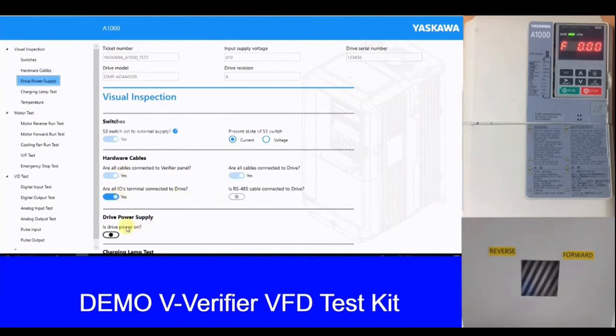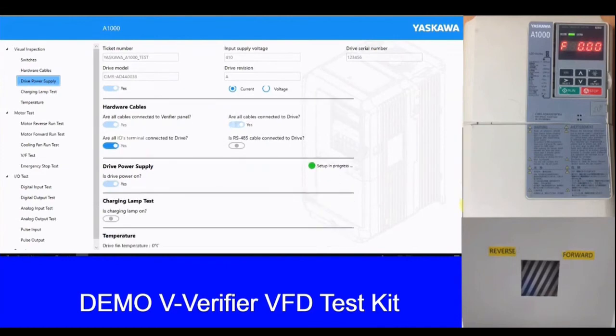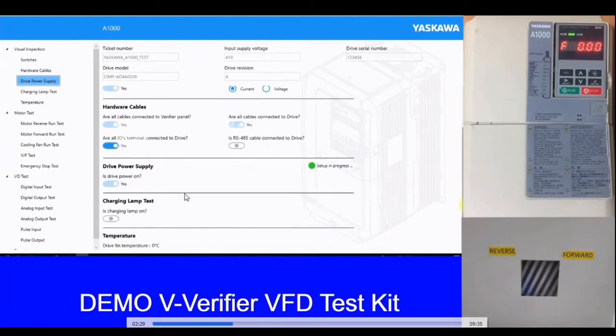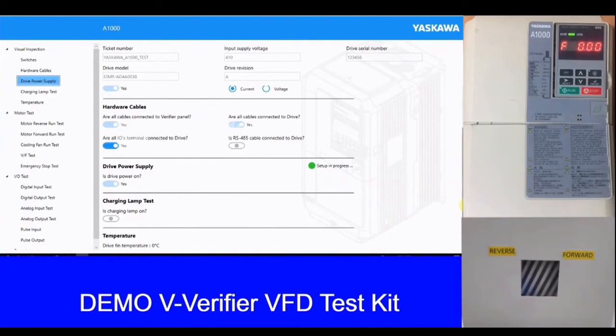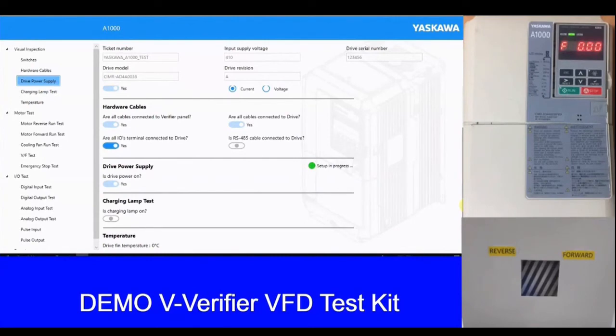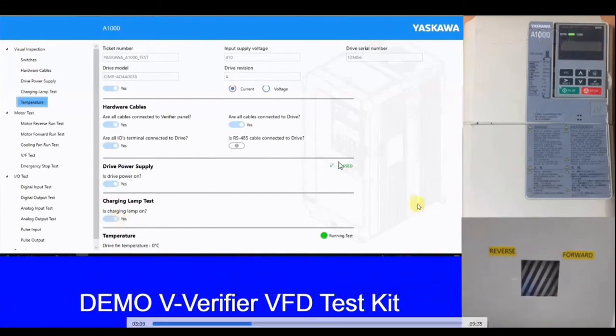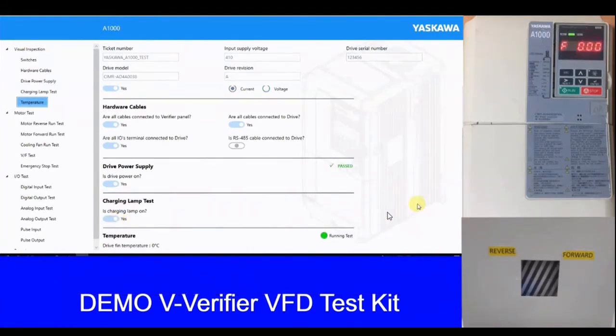Once everything is connected, we press the drive power on button. The initial setup in the VFD begins — required parameter verification and other checks will start. This will take some time. Once the initial setup is complete, we proceed with the charging lamp test, which is a physical verification of whether the charging lamp is working. The service engineer physically verifies if the charging LED is on and selects yes or no.